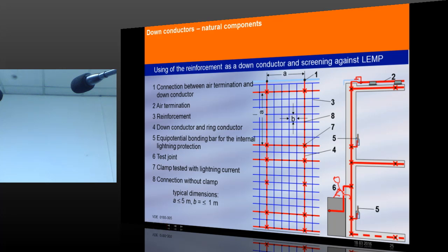Generally, in those buildings, between the soil and RCC, a thick plastic sheet is provided to avoid water seepage. So, let's say this is a water insulation, if water insulation with a plastic material is provided for this particular building, will it dissipate the current? No. So, this is one of the conditions. In that particular case, we need to have an extended external ring conductor.